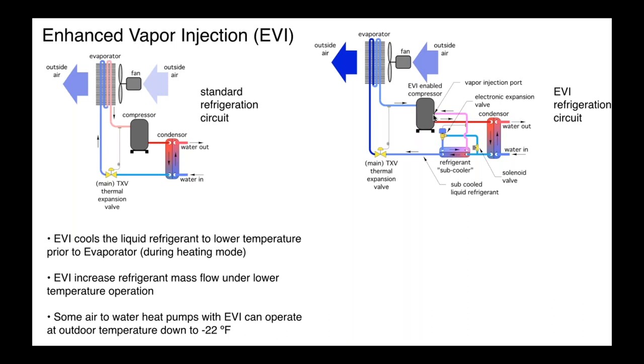There's at least one manufacturer on the market now that rates the product to operate down to minus 22 degrees Fahrenheit. And even in cold northern climates, you're perhaps going to see that a few hours a day. So this has really changed the picture from what air source heat pumps used to be viewed as. Back in the 80s and the 90s, the idea was, well, air source heat pumps are good. They work in southern states. They might work up in places like Pennsylvania, Maryland, and so forth. But what about Caribou, Maine? Or what about Milwaukee or other cold climate applications? Well, air source heat pumps had a connotation. They really weren't suitable for those climates. This has really changed the game quite a bit.